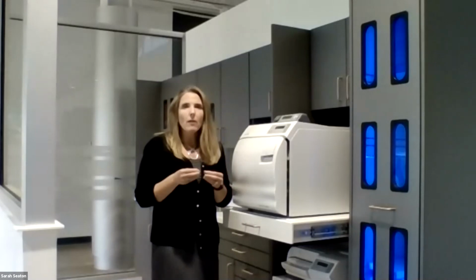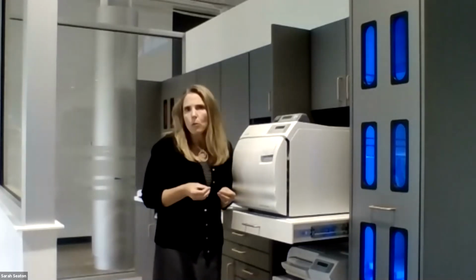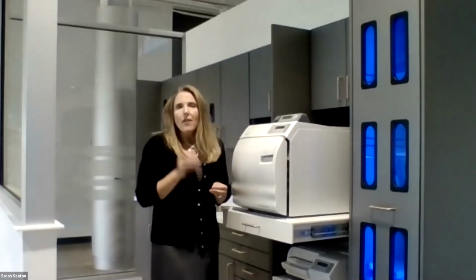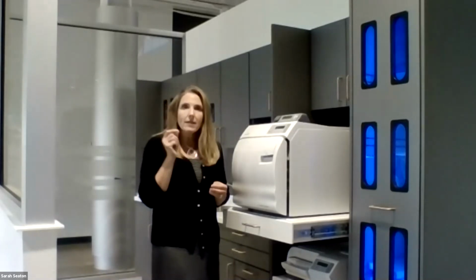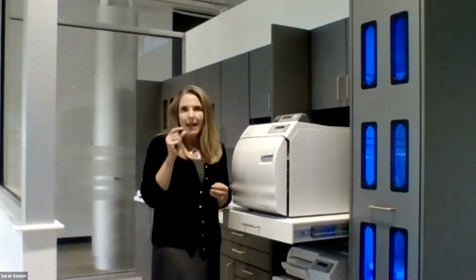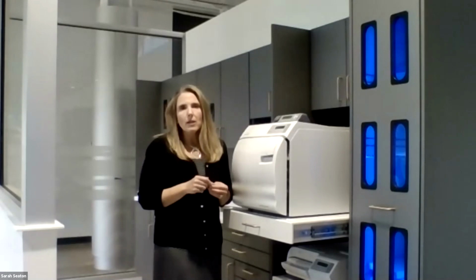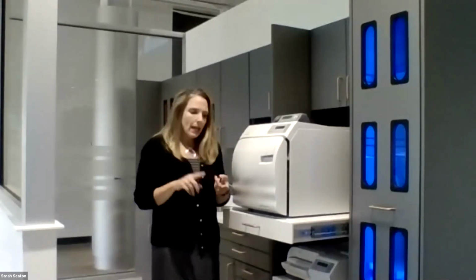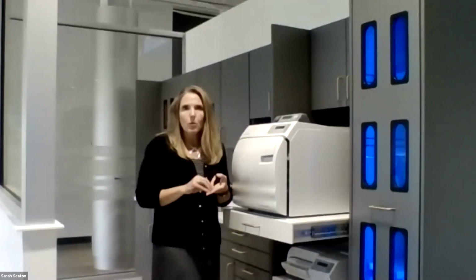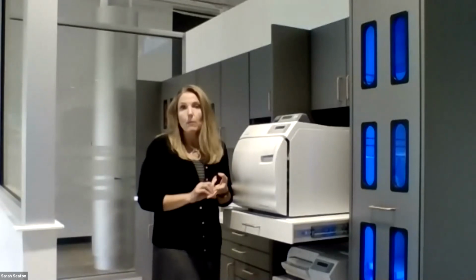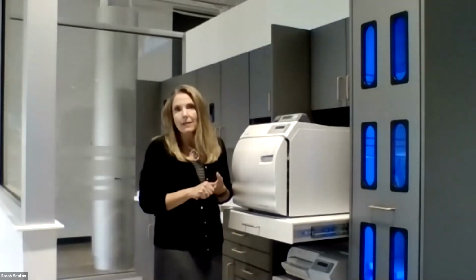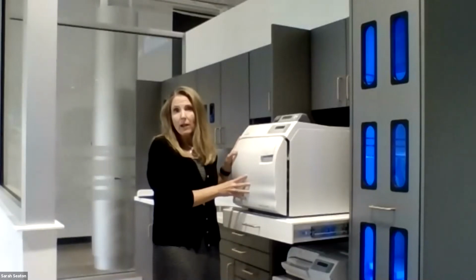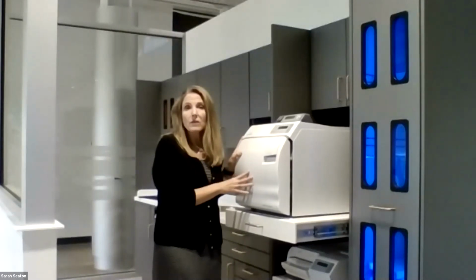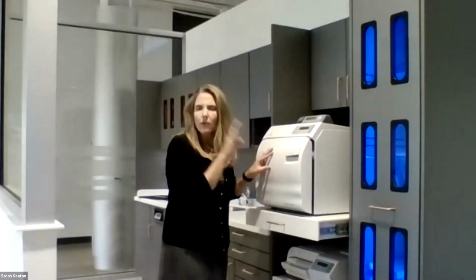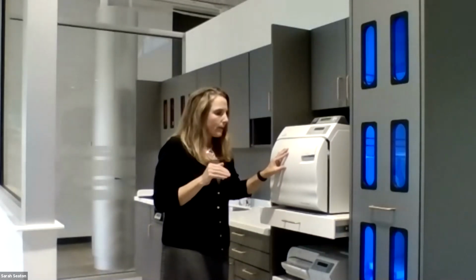And then the biological indicator is really where the rubber meets the road from a sterility perspective. That's telling you that the sterilizer is killing the spores in that test. And you really want to make sure that your unit is properly maintained and that we're killing those spores on a weekly basis at a minimum, which is the recommendation from the CDC. Okay? And you need to keep those records as long as your local state authorities indicate. Every state has different regulations for that.